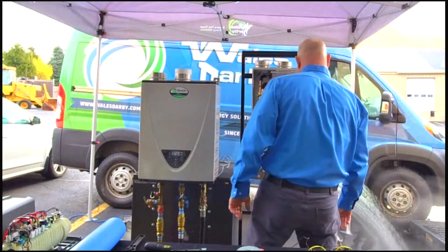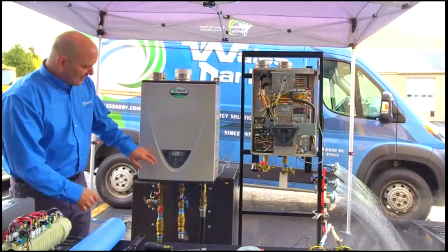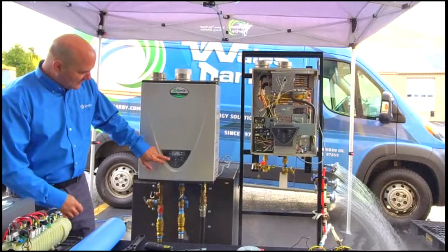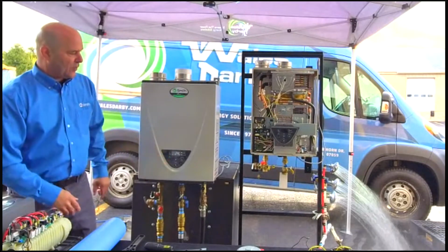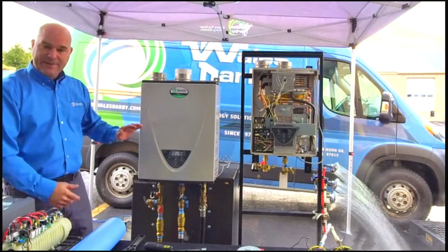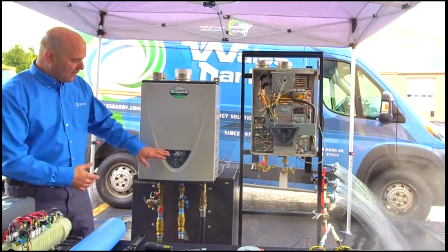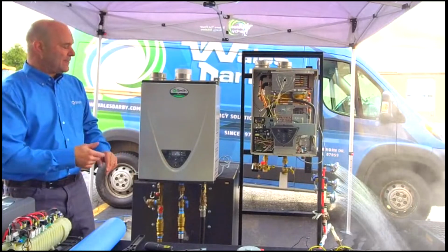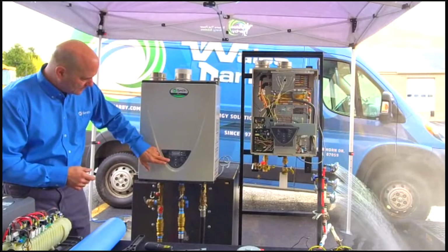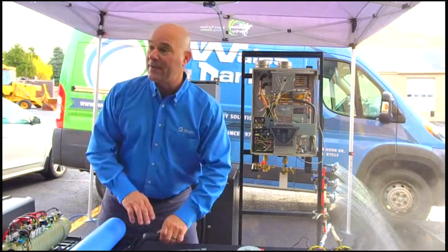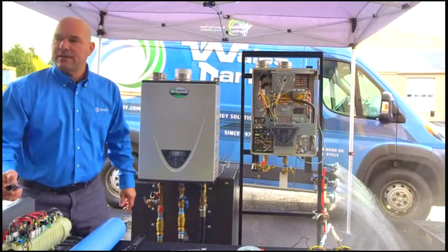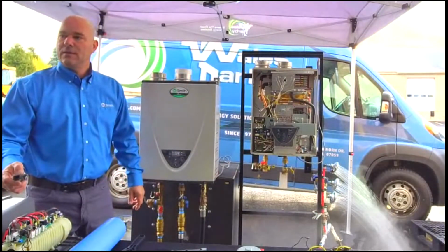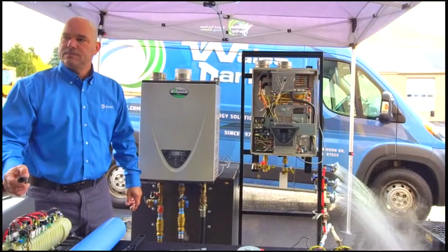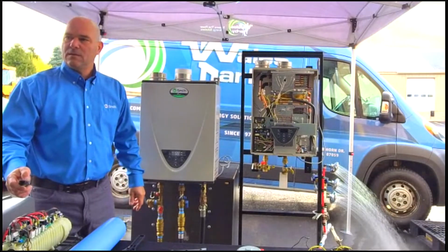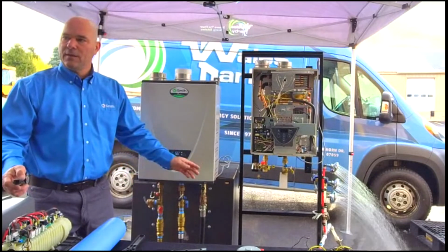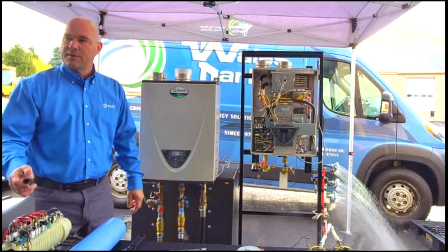And we are really stressed for water now if there's people in the building. We had a little higher flow rates this morning when no one was in the building, but we're at 2.5, 2.4 gallons of flow. So the unit is modulated down. If we had more flow right now, we could be 5.4, 5.7 with, what was our temperature coming in? So it's 54 degrees coming in. I'll tell you exactly where we would be if we had greater flow. But we will run and deliver that target temperature until I run this tank out of propane.